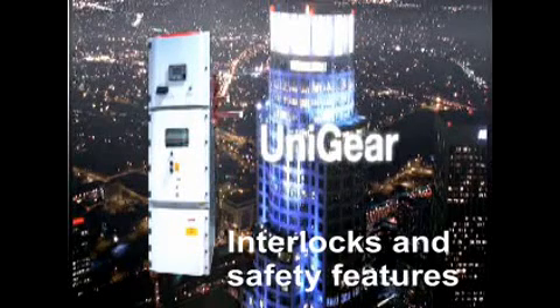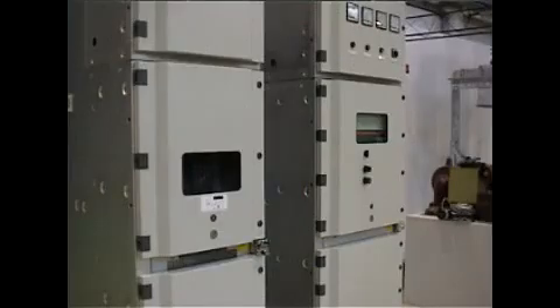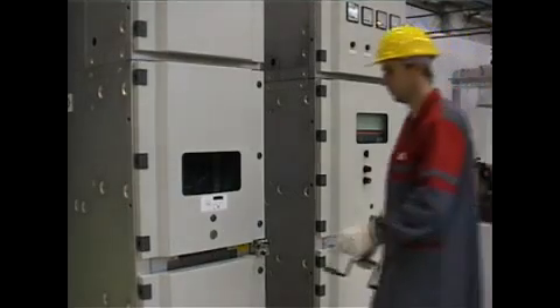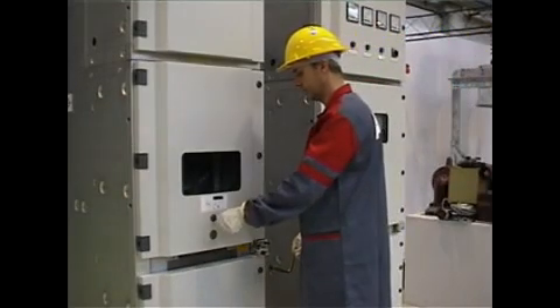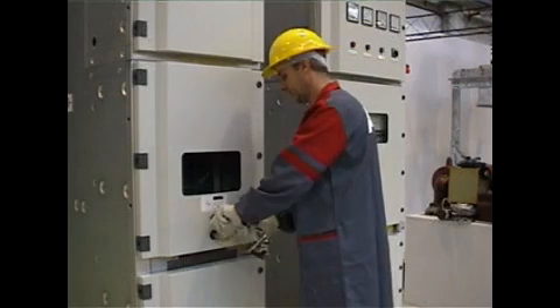UniGear is fitted with an array of interlocks and features in order to improve the safety level and to reduce the risk of incorrect operation. We would like to show you the complete sequence needed to withdraw the circuit breaker and access the cable compartment, and then we will put the switchgear back into working condition.